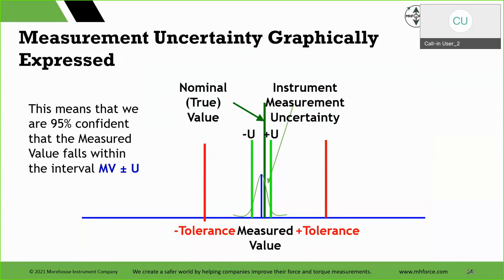For those who see this and that poll is up for them, it is our next slide. I jumped the gun, and we'll have enough time to answer it. So, measurement uncertainty graphically: the nominal true value is the green line here. You have your measured value, and you have your true value, which, if you're using dead weight, is 10,000 pounds. It still has some error; we know it to 0.0016%. Then you have your uncertainty, and then your tolerance specifications. This means we are 95% confident that the measured value falls within the interval of the measured value plus or minus U. And that's what we're showing graphically.